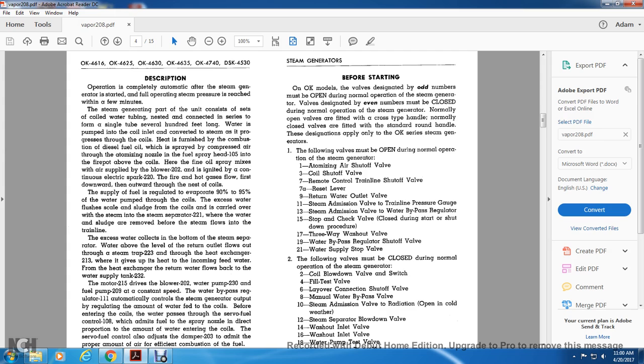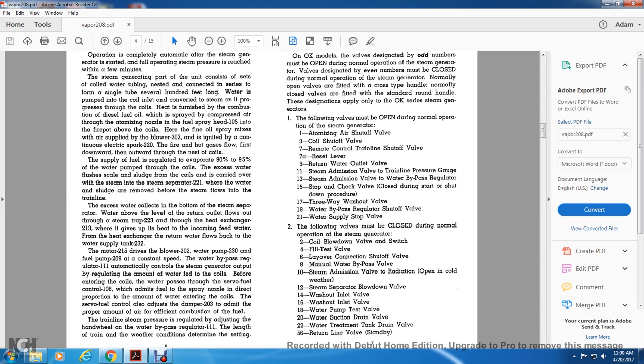The excess water, along with sludge and scale from the coils, is carried over with the steam to the steam separator 221, where the water and sludge are removed from the steam flow to the trim line. The excess water collects at the bottom of the steam separator. Water above the level of the return outlet flows through the steam trap 223 and through the heat exchanger 213, where it gives up its heat to the incoming feed water. From the heat exchanger, the return water flows back to the water supply tank 232.